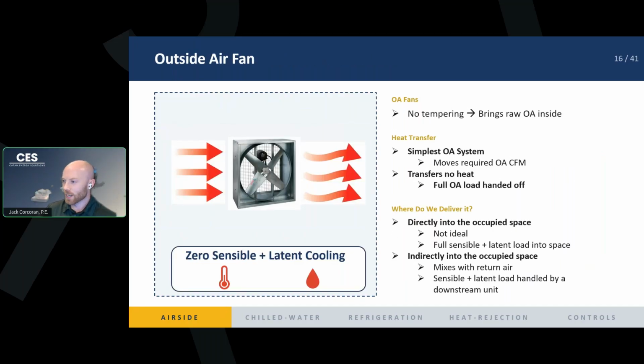Right. And so when we look at these, with these principles in mind, we can look at our different types of systems, right? We have our outside air fan. There's zero sensible and there's zero latent cooling, right? And so if you can picture the psych chart, we're not moving our outside air from 95, 75 anywhere along the chart, right? Whatever the sensible heat ratio of the space is, we're going to move along that diagonal line.